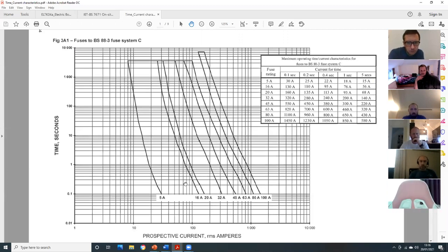So first of all, realize it's an odd scale. It's what's called a logarithmic scale. 1, 2, 3, 4, 5. You can see as you get towards the upper range, they get closer together. And likewise, 10, 20, 30, 40, 50 is not halfway. These portions aren't equal amounts. It's to enable you to get a large amount of data, like in the 10,000s of amps, in the 10,000s of seconds, 2 3/4 hours, 10 kA, onto a small A4 sheet of paper.